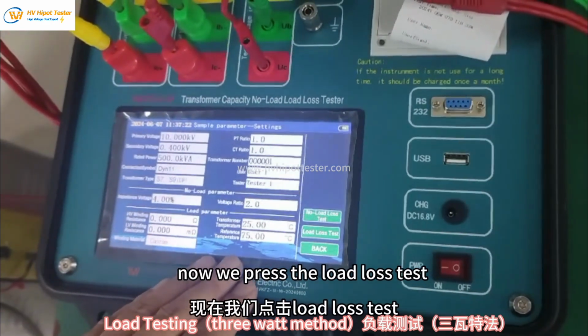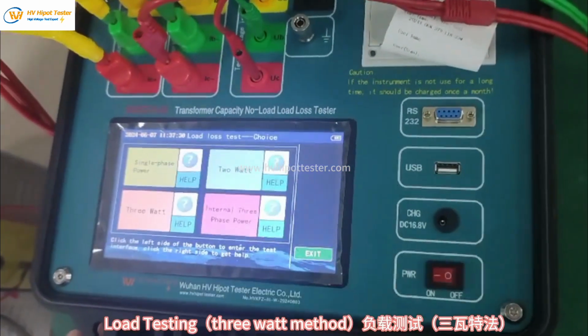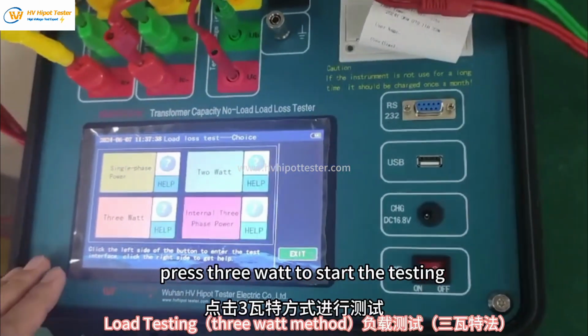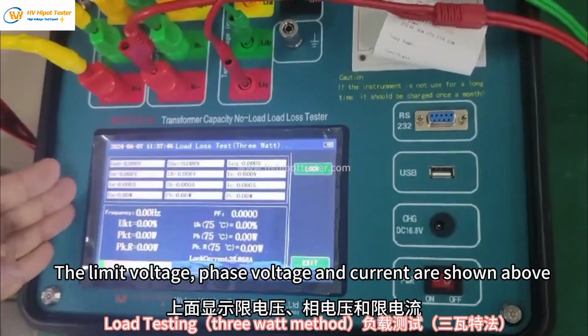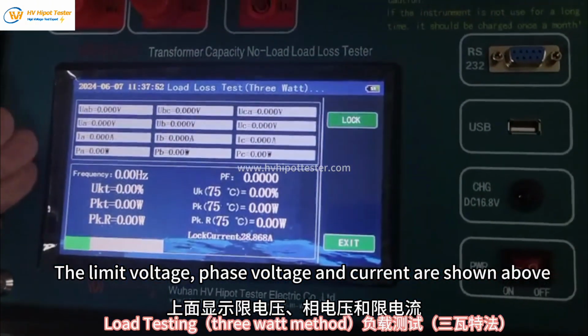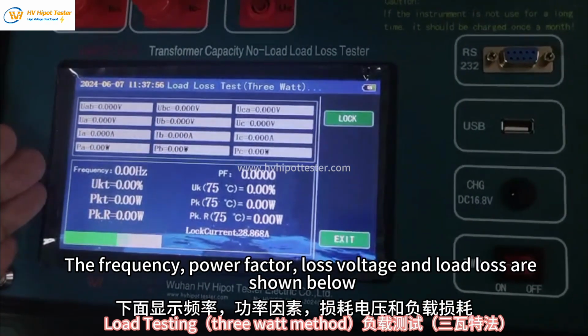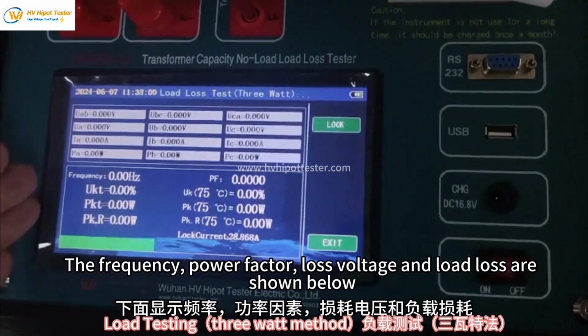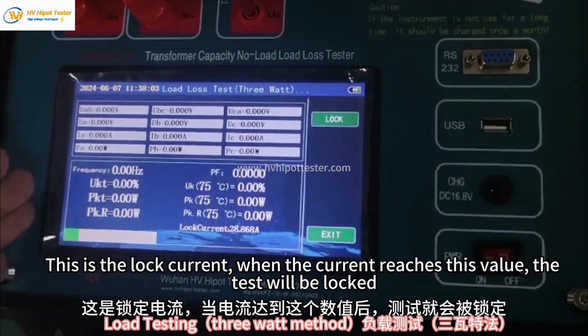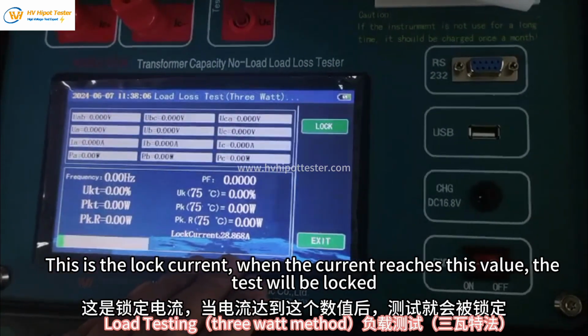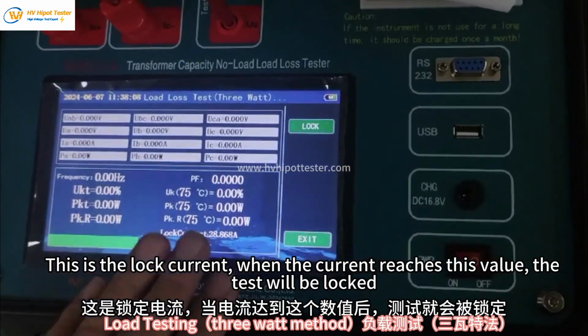Now we press the load loss test. Press 3 watt to start the testing. The line voltage, phase voltage and current are shown above. The frequency, power factor, loss voltage and load loss are shown below. This is the lock current. When the current reaches this value, the test will be locked.